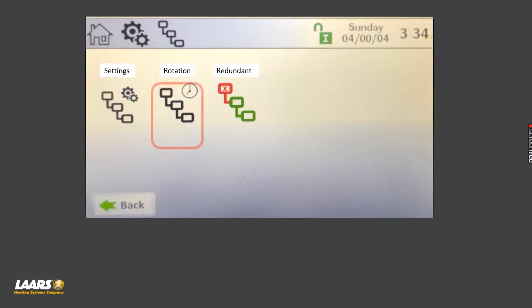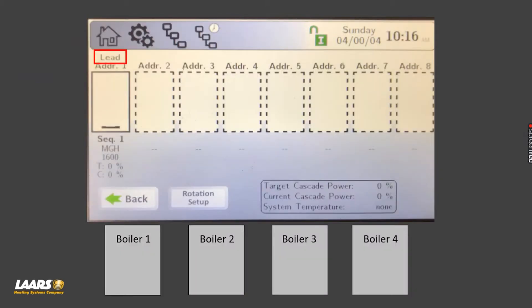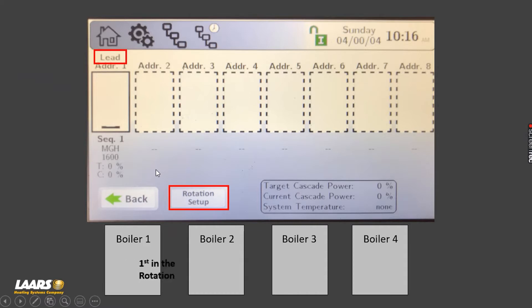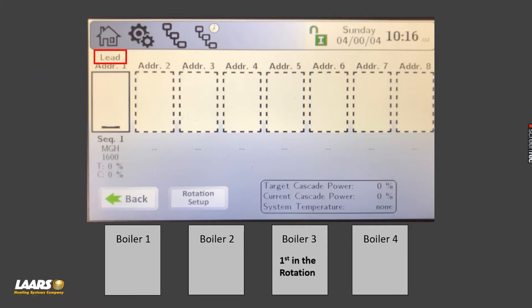Next we'll talk about rotation. When you choose a leader on that lead boiler, another box will appear called rotation setup. Rotation setup is basically to rotate the boilers evenly to get even run time. For example, today boiler one is first in rotation, tomorrow boiler two would be first, the next day boiler three, then boiler four — and again we can cascade up to eight boilers.